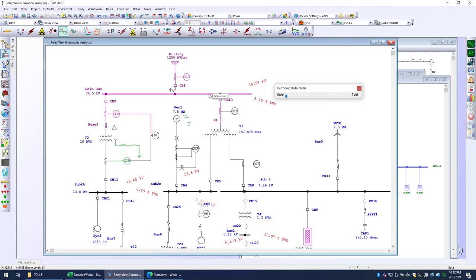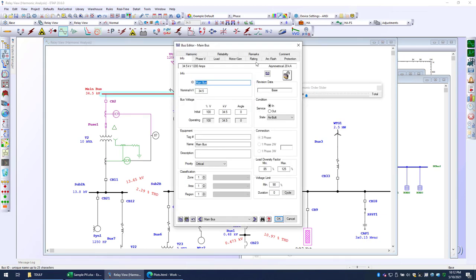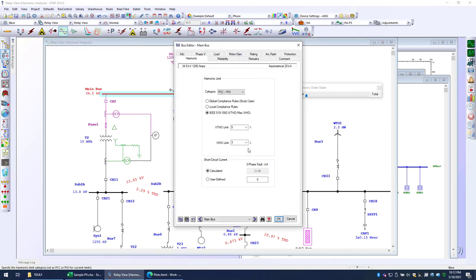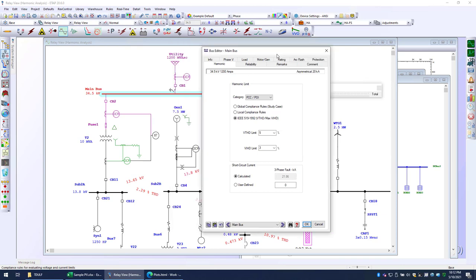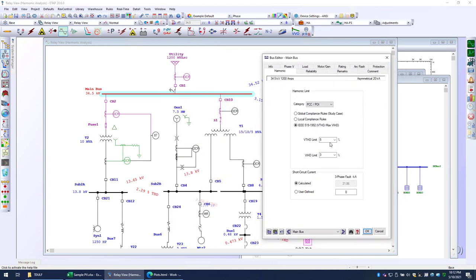Another additional item is that if you are trying to comply with IEEE 519, for example, you can go into your point of common coupling or main bus. You can head over to the harmonics tab and select the category. In this case, this is the PCC or point of common coupling. And I want to set my limits based on the IEEE 519 standard. So for this particular voltage, my total harmonic voltage should be no more than 5%, and individual harmonic distortion no more than 3%.